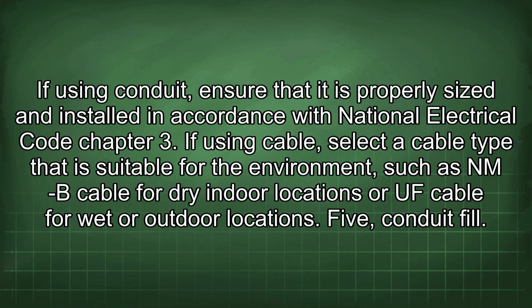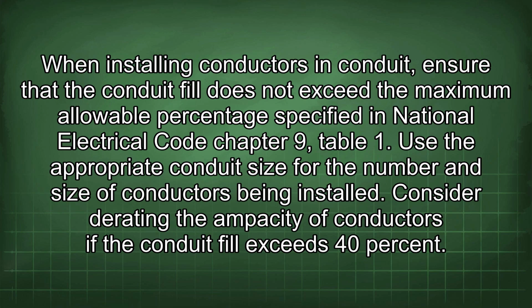5. Conduit fill. When installing conductors in conduit, ensure that the conduit fill does not exceed the maximum allowable percentage specified in National Electrical Code Chapter 9, Table 1. Use the appropriate conduit size for the number and size of conductors being installed. Consider derating the ampacity of conductors if the conduit fill exceeds 40%.